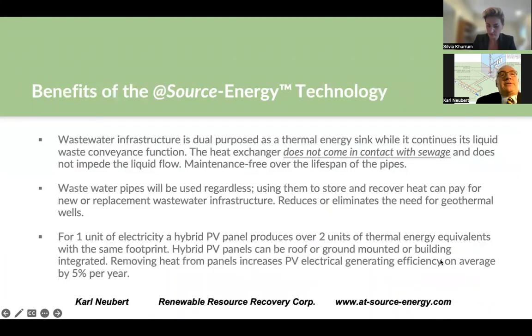The benefits of the @Source-Energy technology are, first, wastewater infrastructure is dual purpose as the thermal energy sink while it continues its liquid waste conveyance function. The heat exchanger does not come into contact with sewage and does not impede the liquid flow. The sewage pipe is maintenance free over the lifespan of the pipes. Pipes have a minimum lifespan of 50 years. We know of some in New York City that are over 120 years. So this is the expected life expectancy of the heat exchanger in the sewage pipes.